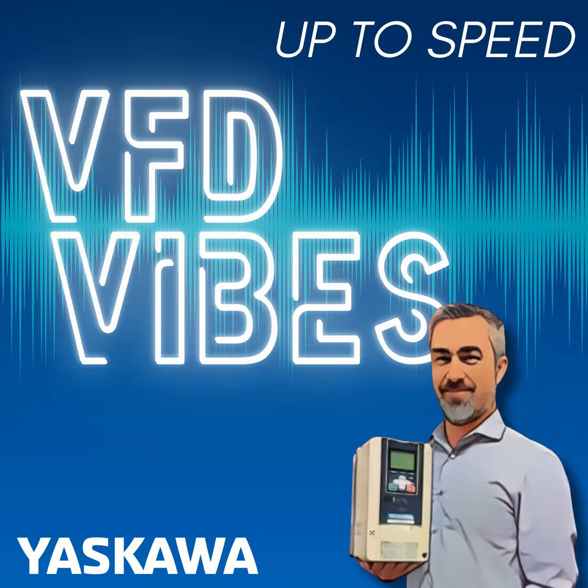Yeah. So far, we've gone through our initial auto tune. What are some of the other common parameters that we tend to adjust at startup? Yeah, when you're starting up a drive, you need to apply a run command and a speed reference. The drives are factory configured to look for a run command on S1 and SN. That probably sounds familiar if you've worked on a Yaskawa drive. That goes back several generations.